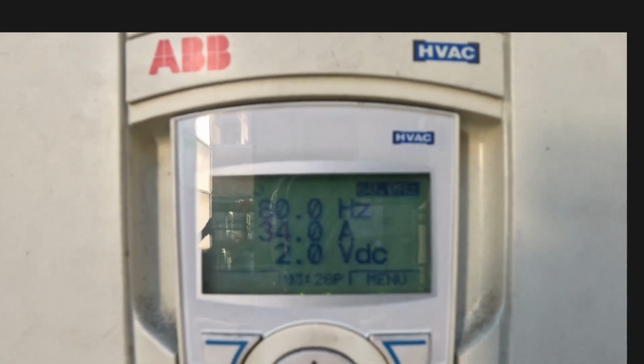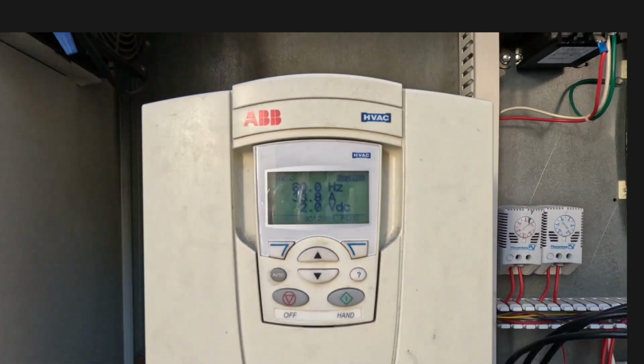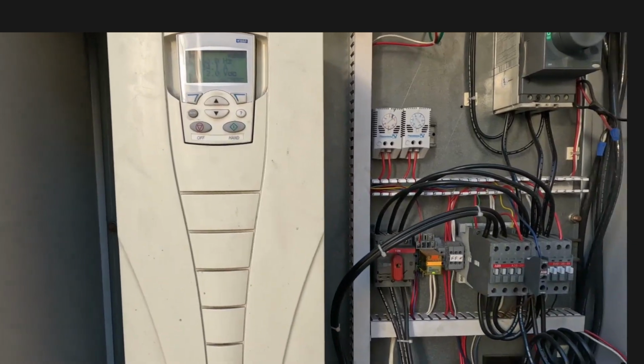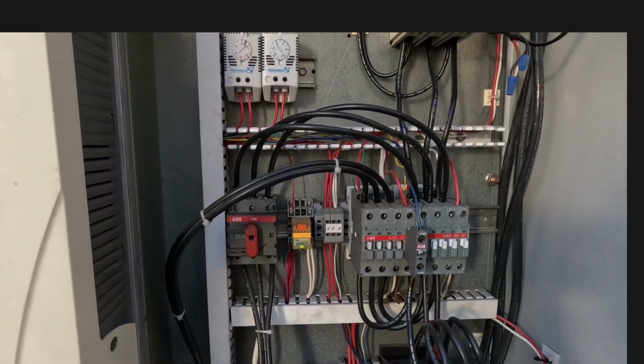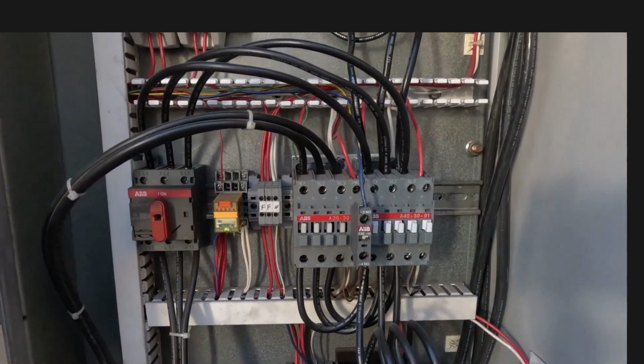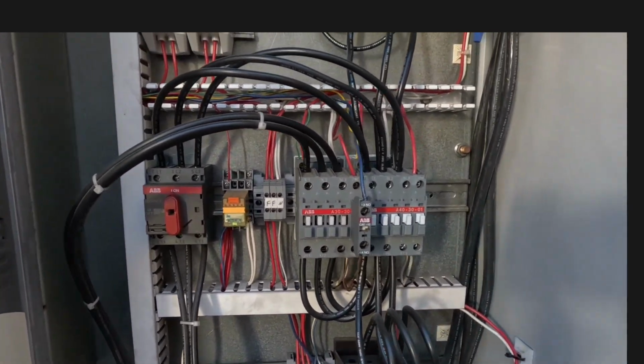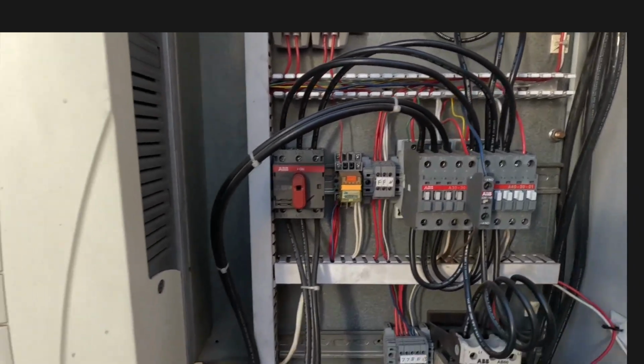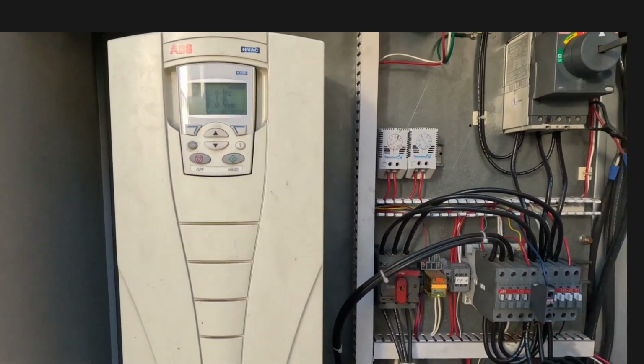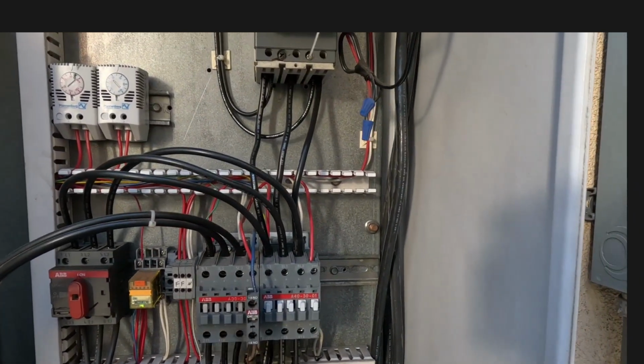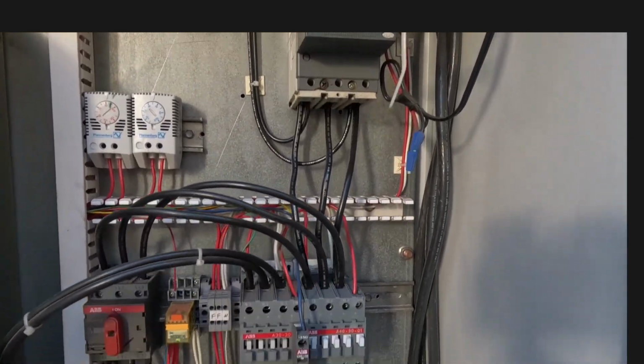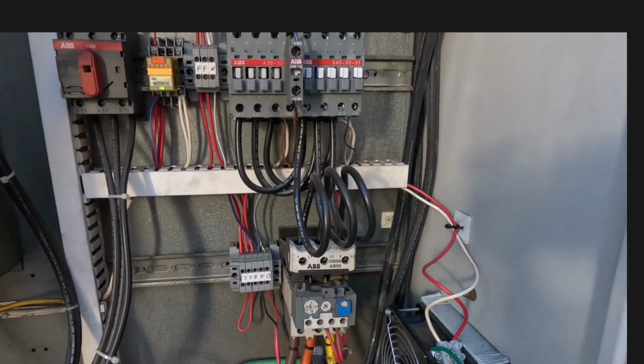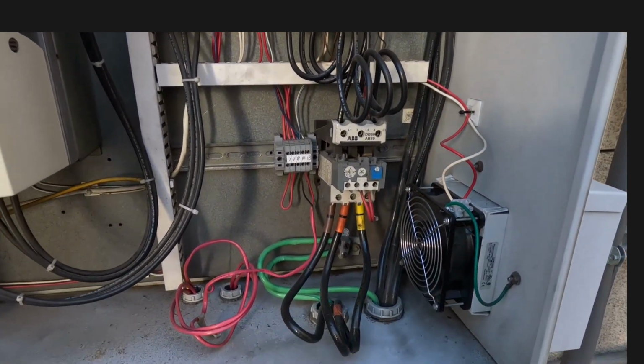I'm running this VFD 100% in order to maintain the load while I have one cooling tower off and I'm working on it or servicing it. So here you've got contactors. You've got a contactor for the VFD, and then you've got a contactor that goes straight through. You decide to just give it 100% power with no speed control.